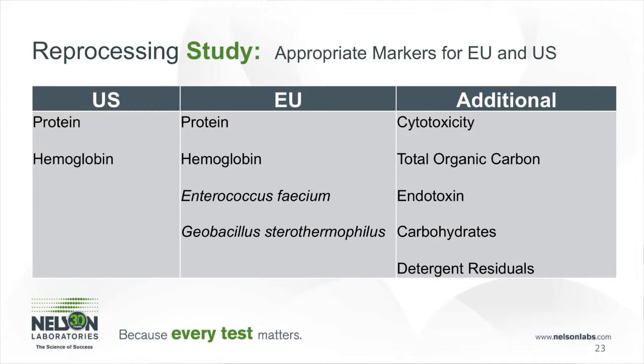The EU is now asking for bioload reduction of a spore-forming organism, which is mainly Geobacillus stearothermophilus, and also Enterococcus faecium. And they're requiring that for all submissions for the EU, specifically for the Bavarian government. So we've seen this become very popular in the last few years or months, and so that's what we recommend for EU testing. Other tests that may be performed would be cytotoxicity to determine if there are any residuals left on the devices, as well as endotoxin testing if the device is coming into contact with any cerebral spinal fluid or brain tissue.